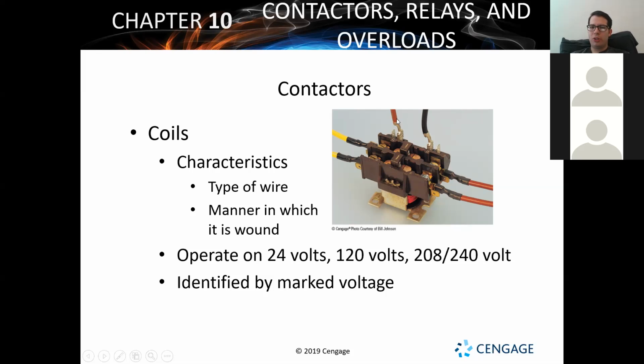All right, so if we throw electricity, power comes in, let's say through this lead, it's going to go down underneath this, go through that coil, and then come back out. Now, that's going to create a load, so now I'm going to see a voltage difference. If this is working, I should see 24 volts typically for control voltage. Sometimes you will have coils that run on 120. That's what you're going to see between this lead and this lead, 120 volts. It's usually with much larger equipment. But the 24 volts that we're looking for is going to let us know that, yes, it's getting power.